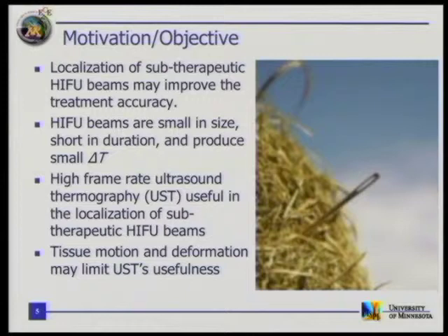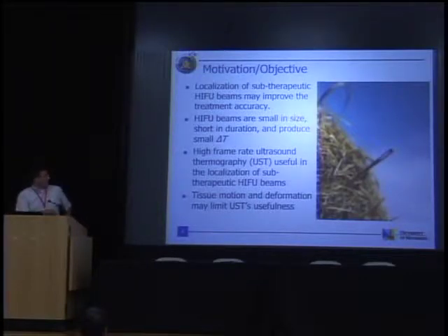The HIFU shot is typically 1 second or even less for coagulation. And we'd like to detect that in subtherapeutic mode. So the high frame rate, and again, it's all relative. My high frame rate at this point is in the hundreds of frames per second. We'd love to go to the thousands if that's necessary, but for this approach, we're trying to maximize the frame rate to capture the tissue motion and deformation so that we can try to separate them. As you'll see today, it is kind of a needle in a haystack. And the beauty of ultrasound is that you really can find that needle, regardless of that.